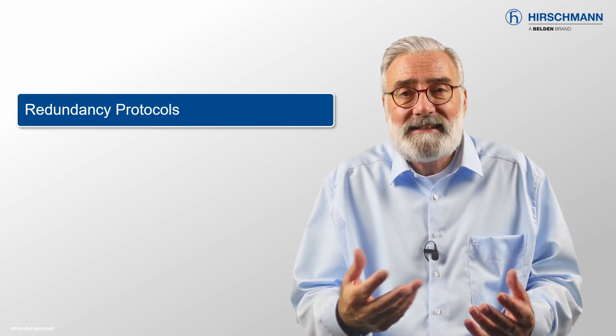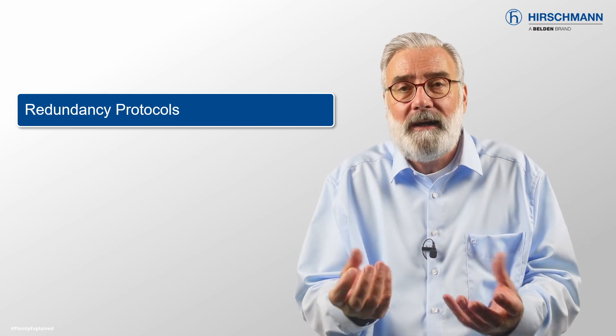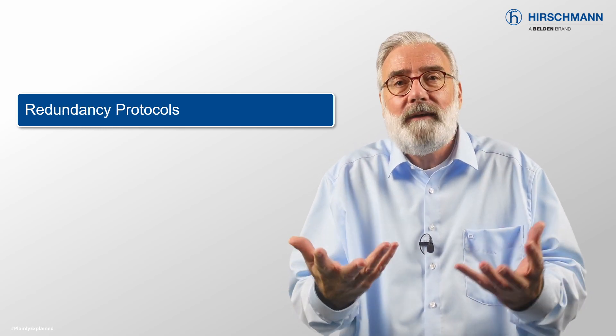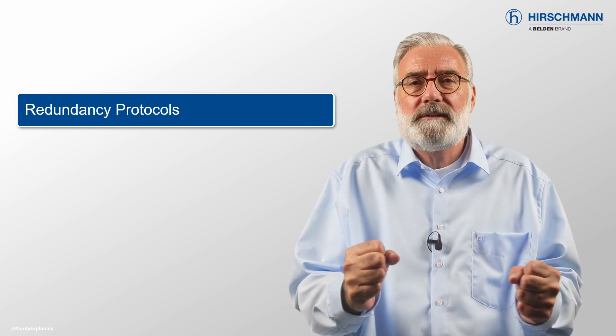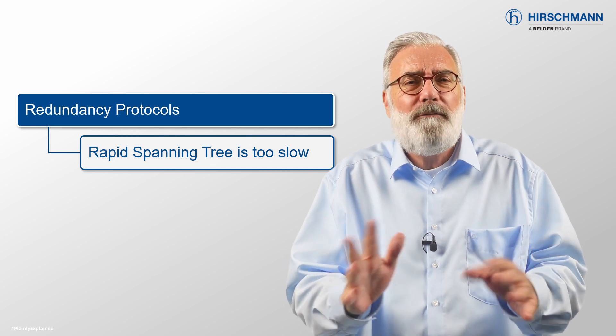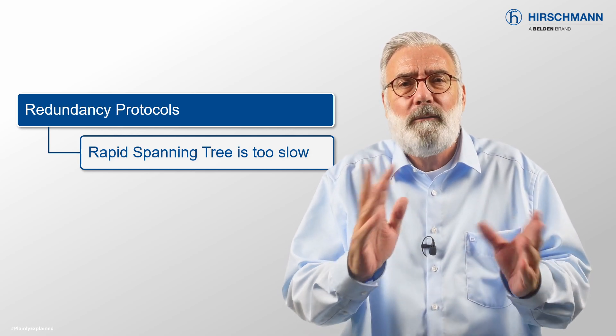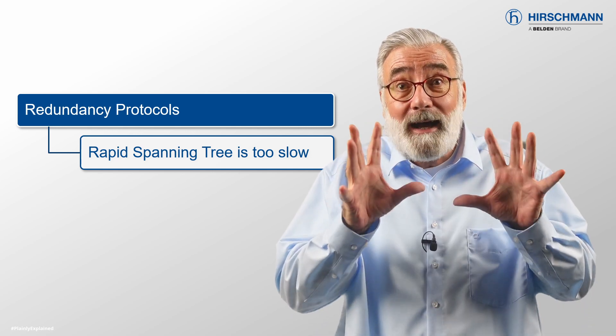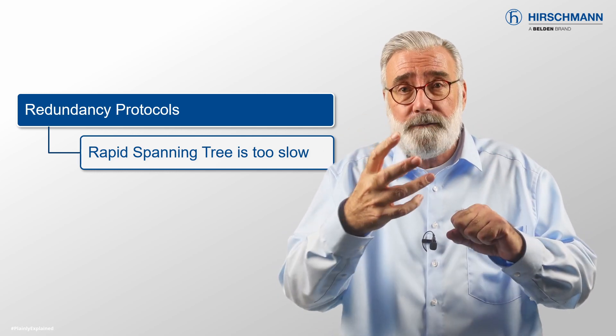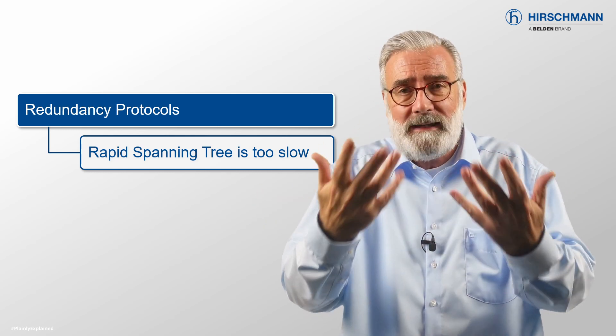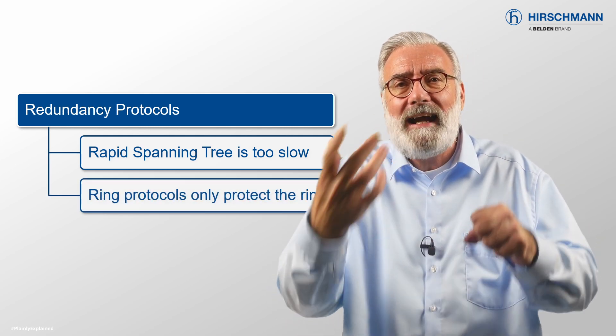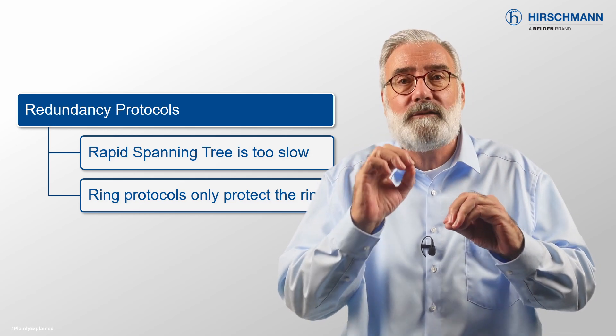While redundancy protocols like SpanningTree work well in an office environment, they lack characteristics which are essential in an industrial environment. First, the mesh topology which is commonly used with SpanningTree is often not practical for industrial networks. Second, industrial applications are time sensitive and they cannot tolerate the slow or unpredictable recovery times which are typical of office redundancy mechanisms. This is the reason why industrial networks typically use standardised or proprietary ring-based redundancy protocols.